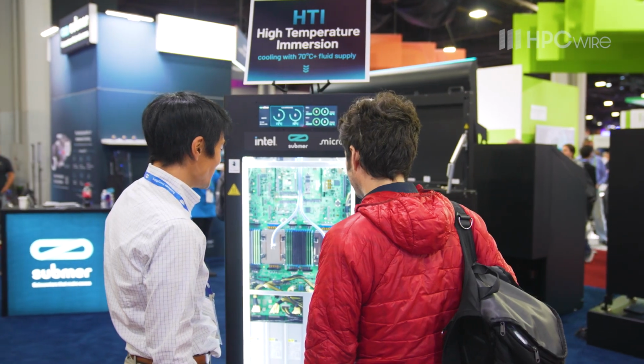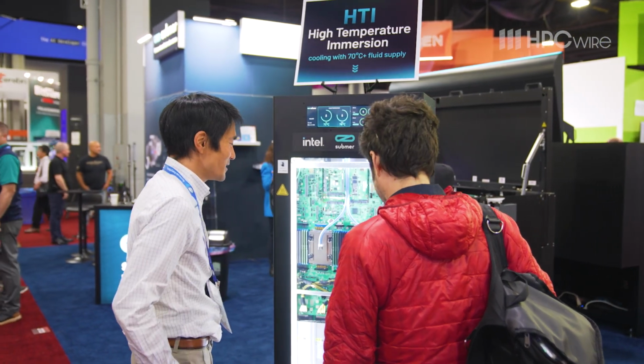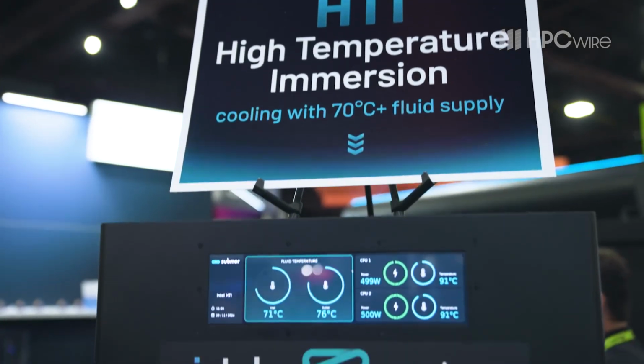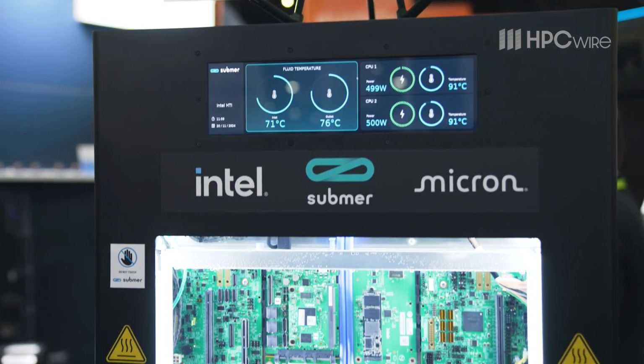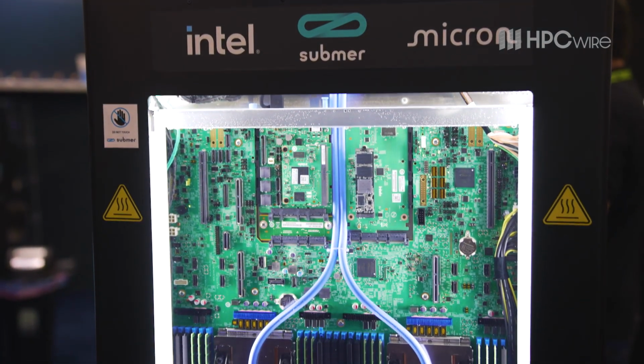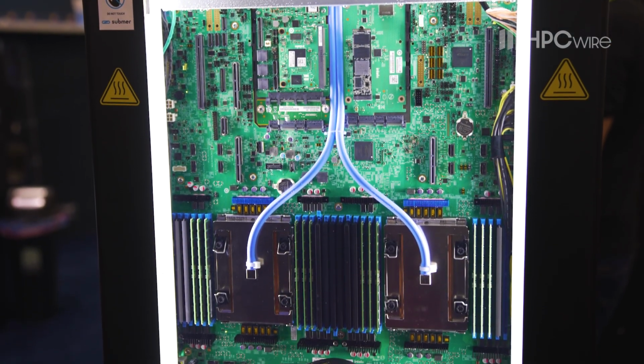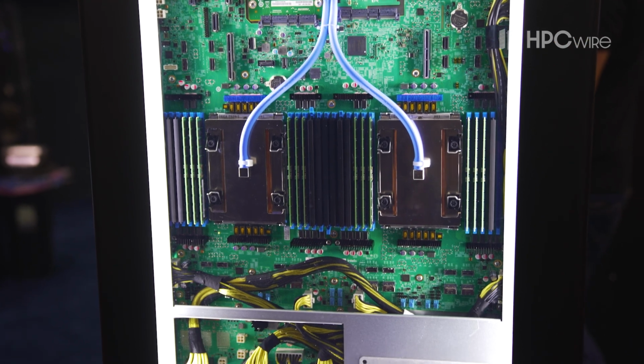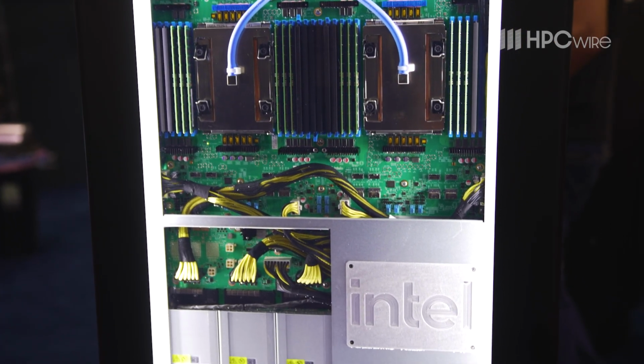The primary benefit is thermal performance, meaning you can cool chips with high TDPs, but you can also do stuff like high temperature immersion, or HTI, a concept we've been working on with Intel since the beginning of the year. HTI refers to immersion cooling using a fluid inlet temperature of 60 C or greater. You can do that because the lower power components on a server are designed to be cooled in air, and when you put them in an immersion tank at typical temperatures of 30 to 40 C, they're essentially overcooled. At 60 C, they're perfectly happy.